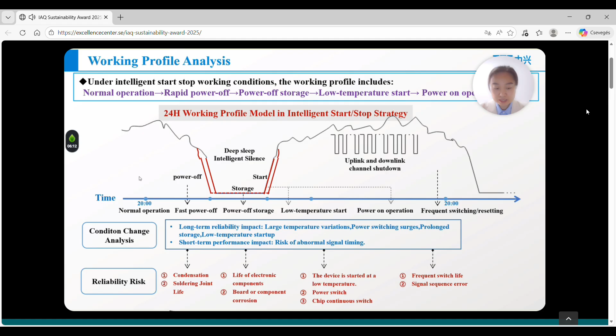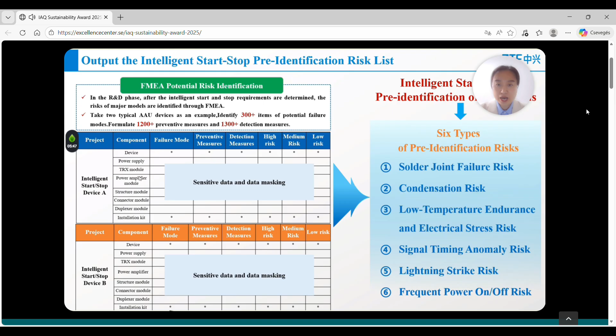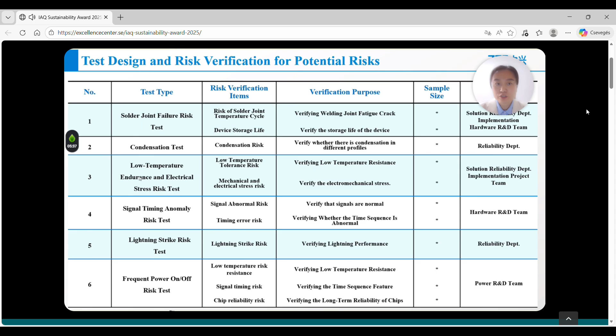Based on the work profile, we identify the risks through the FMEA 7-step method. Take 2 typical AAU devices as an example. We use FMEA to identify 300 items of potential failure modes. In addition, we output an intelligent start-stop pre-identification risk items list, which includes 6 major types of risks. Next, we conduct testing design and risk verification for the 6 major types of risks.